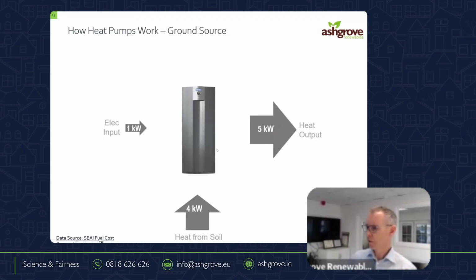Well, in that case, my running cost is even lower than we showed a while ago. Actually, in that case, 7 versus 3.5, it'll be 4 cent versus whatever we said, 14 for oil. So you're talking about 50 or 60 or 70% cheaper than oil. But I would have to say 7 here on the right is unusual. But all the same figures apply. Okay?